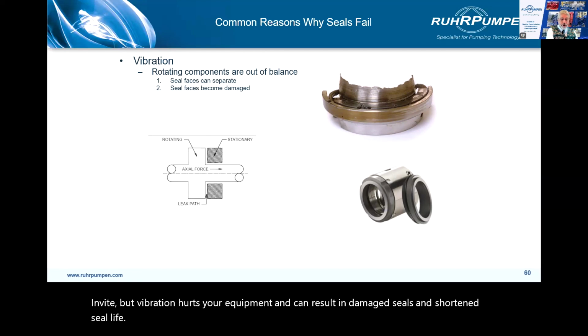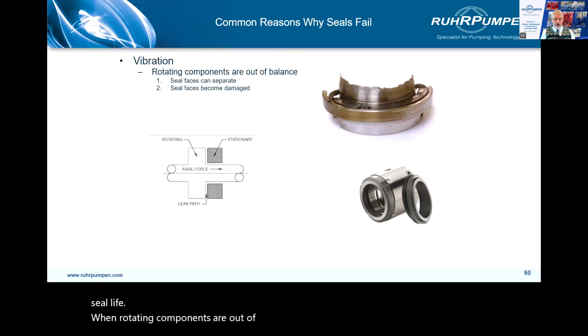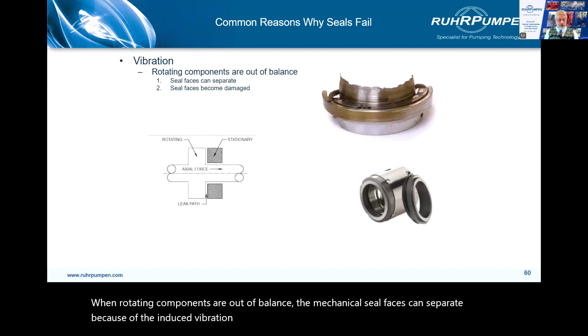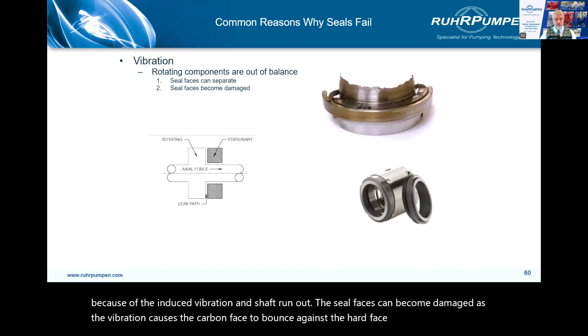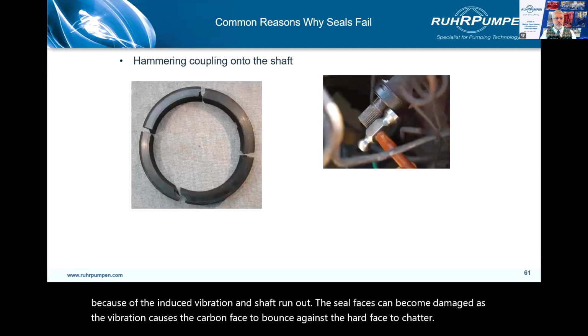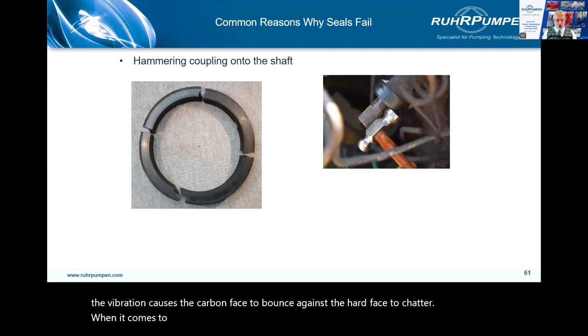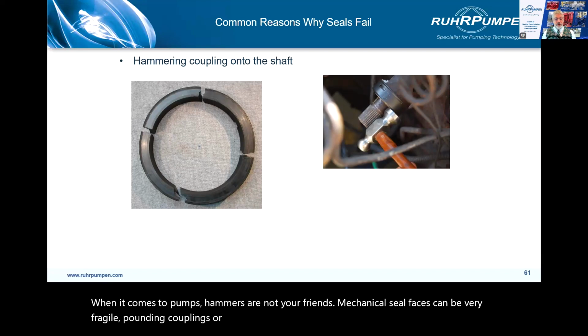But vibration hurts your equipment and can result in damaged seals and shortened seal life. When rotating components are out of balance, the mechanical seal faces can separate because of the induced vibration and shaft runout. The seal faces can become damaged as the vibration causes the carbon face to bounce against the hard face, to chatter. When it comes to pumps, hammers are not your friends. Mechanical seal faces can be very fragile. Pounding couplings or bearings onto the shaft will damage your mechanical seal.